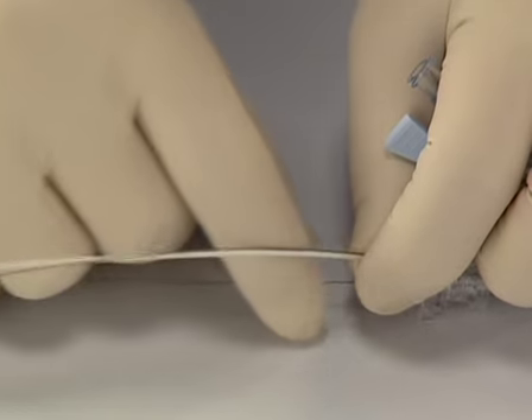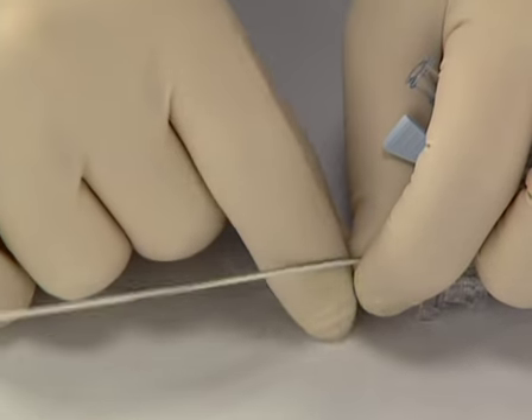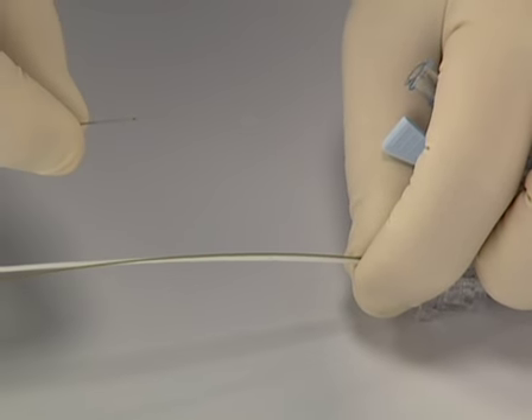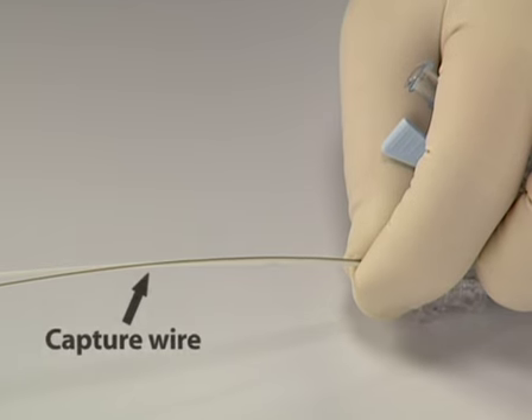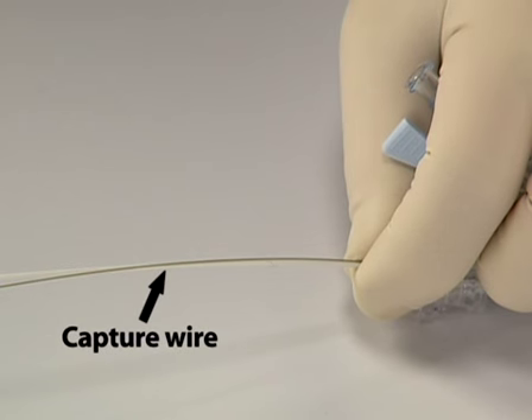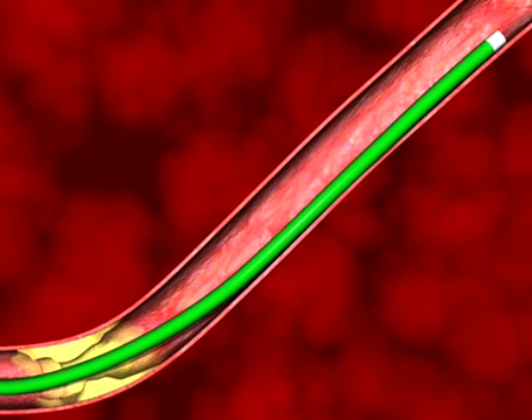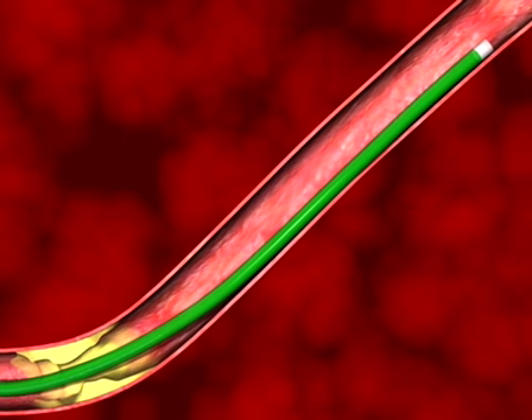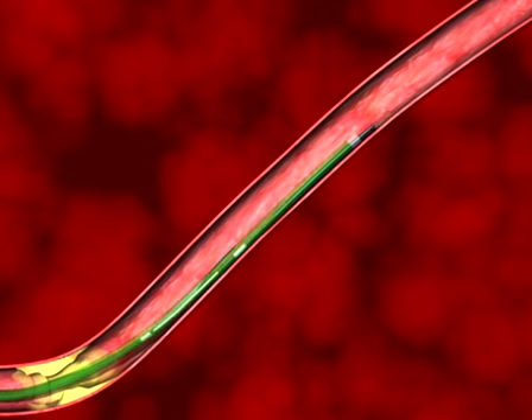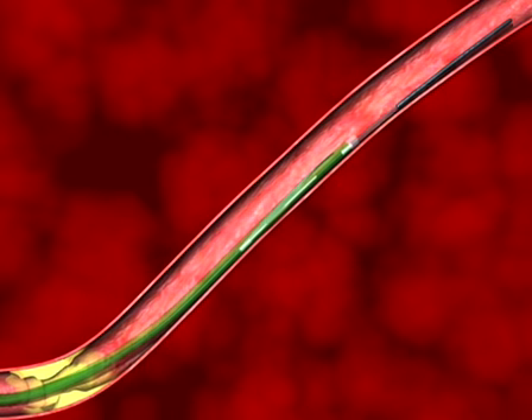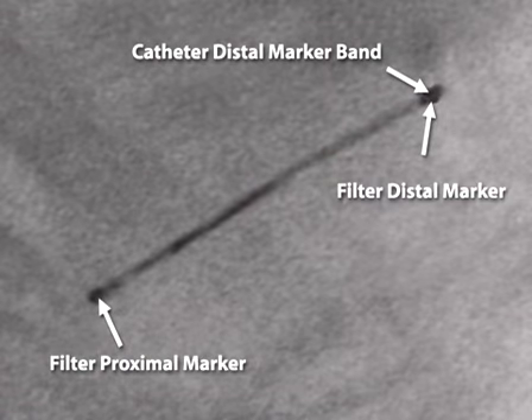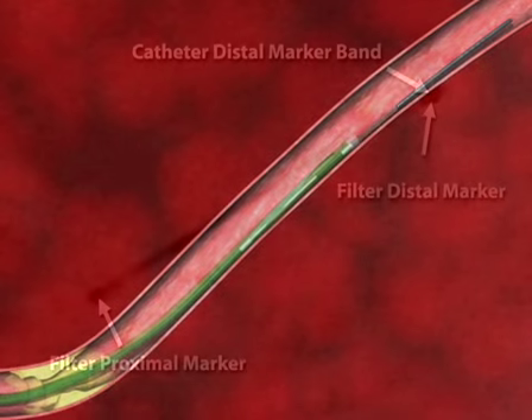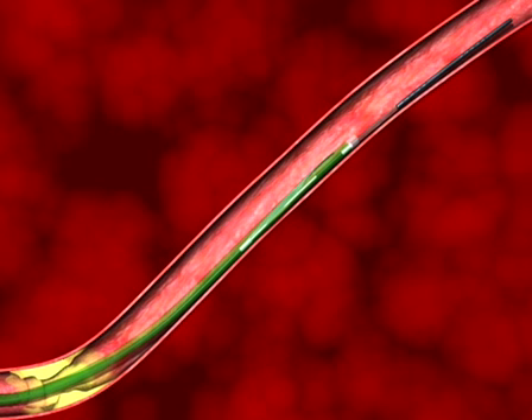Stabilize the Spider FX catheter and gently remove the primary guide wire. The Spider FX capture wire is the working wire for the remainder of the interventional procedure. While keeping the catheter stationary, advance the capture wire until the radiopaque distal filter marker aligns with the distal radiopaque marker band on the catheter. The filter distal tip may be observed extending out of the catheter.